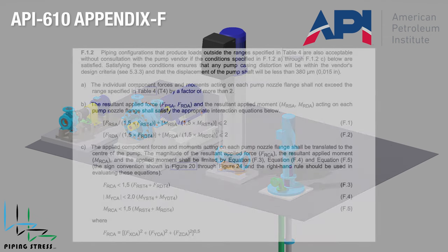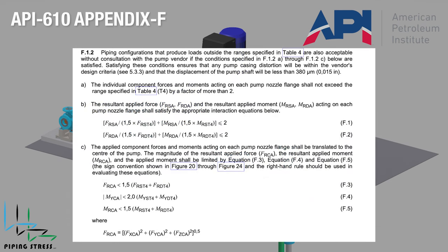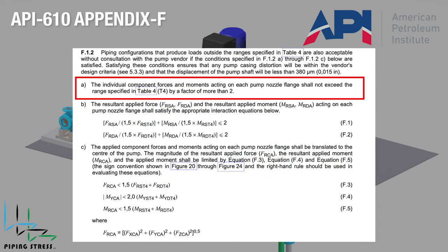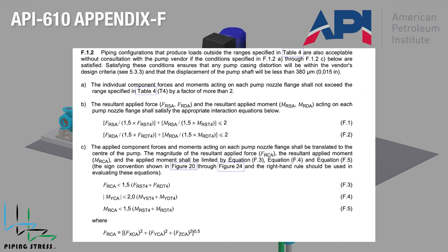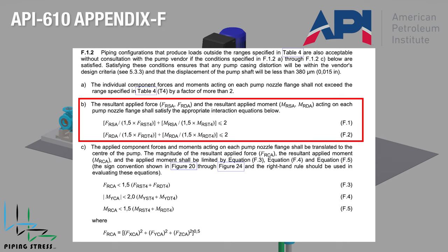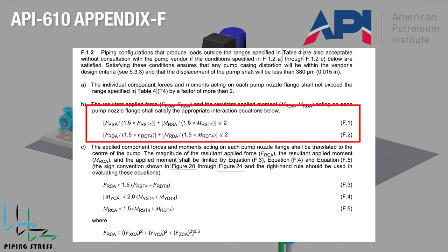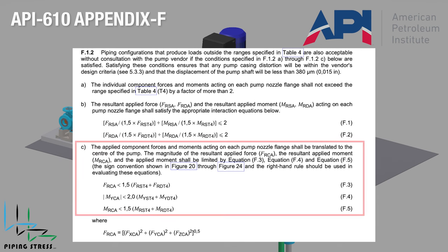The F1.2 conditions are as follows: F1.2A stipulates that all forces and moments acting on each pump nozzle flange shall not exceed the Table 4 range by a factor of more than 2. F1.2B stipulates that the resultant applied force and moments acting on each pump nozzle flange shall satisfy equations F1 and F2. F1.2C stipulates that the applied forces and moments acting on each pump flange shall be translated to the center of the pump.